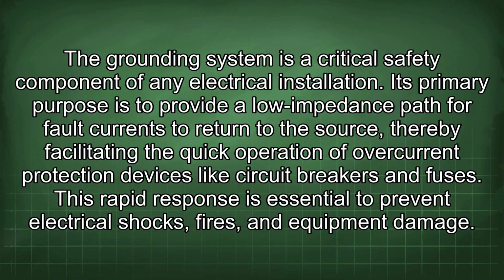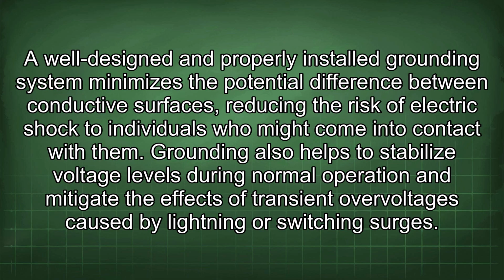Its primary purpose is to provide a low impedance path for fault currents to return to the source, thereby facilitating the quick operation of overcurrent protection devices like circuit breakers and fuses. This rapid response is essential to prevent electrical shocks, fires, and equipment damage. A well-designed and properly installed grounding system minimizes the potential difference between conductive surfaces, reducing the risk of electric shock to individuals who might come into contact with them.